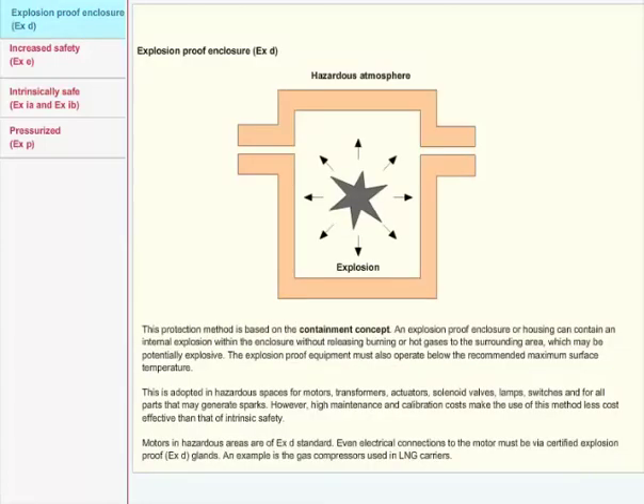Explosion-proof enclosure, Ex d. This protection method is based on the containment concept. An explosion-proof enclosure or housing can contain an internal explosion within the enclosure without releasing burning or hot gases to the surrounding area, which may be potentially explosive. The explosion-proof equipment must also operate below the recommended maximum surface temperature.